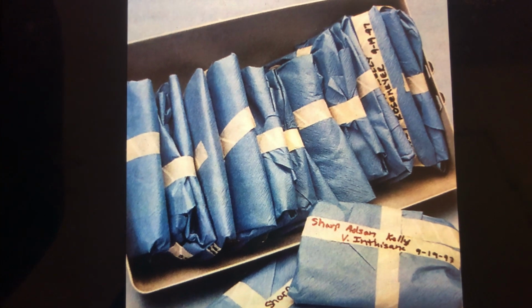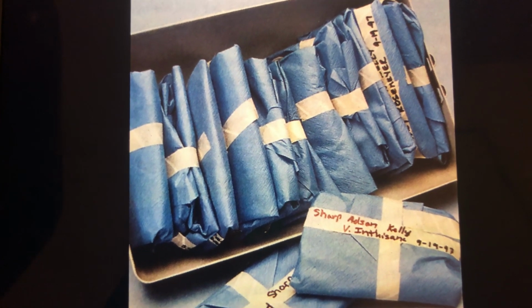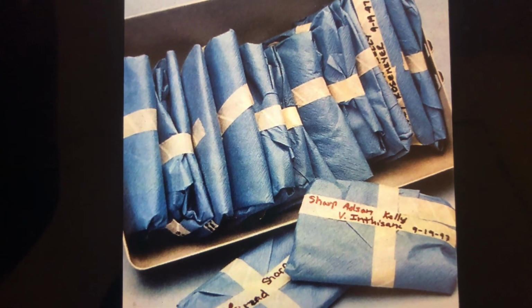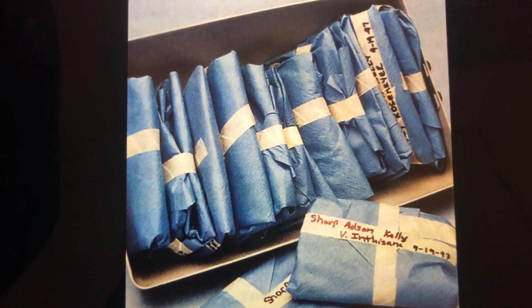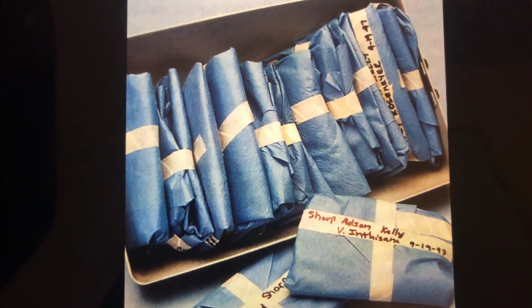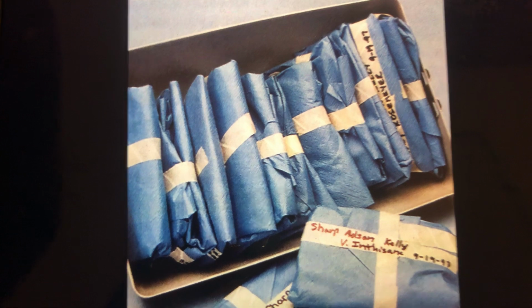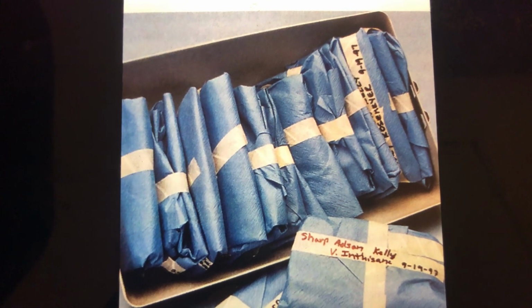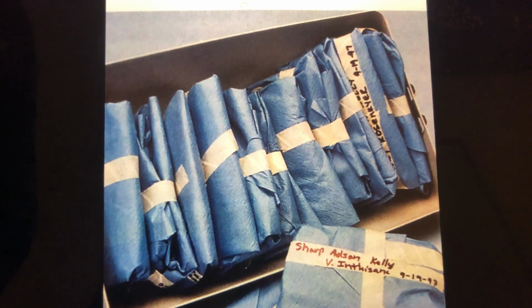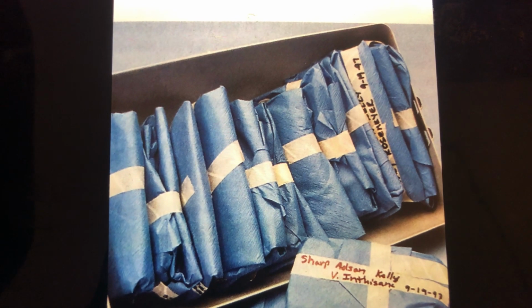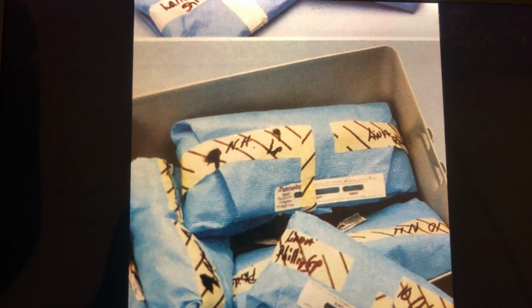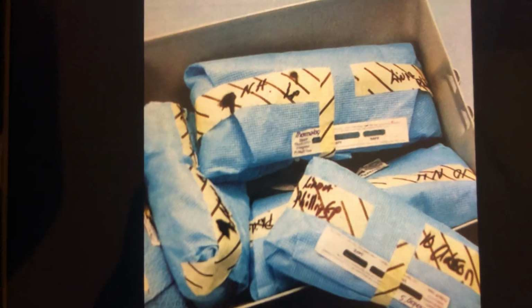Standing behind the autoclave door, carefully open the chamber door one quarter. Leave the autoclave control at vent to continue releasing heat. Allow complete drying of all articles. Using heat-resistant gloves, remove the items from the chamber and place the sterilized packages on dry covered shelves, or open the autoclave door and allow the items to cool completely before removal and storage. Turn the control knob to off and keep the door slightly ajar.